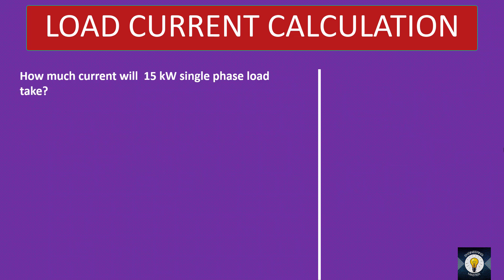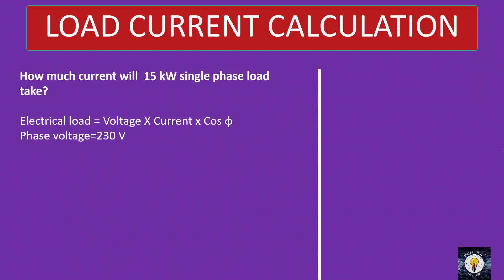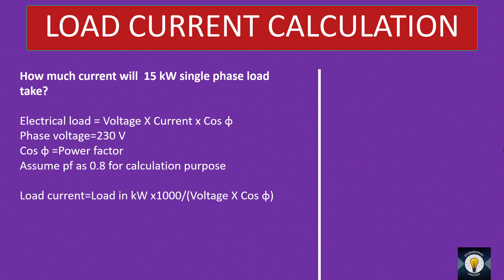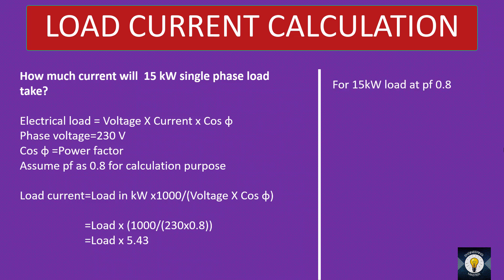In the case of single phase, let's solve a problem. What is the current consumed by a 15 kW single-phase load? For single phase, electrical load equals voltage into current into cos φ. Voltage is phase voltage — my phase voltage is 230 V. Assuming power factor 0.8, load current equals load in kW into 1000 divided by voltage into cos φ — that is load into 1000 divided by 230 into 0.8 — which gives load into 5.43. So for a 15 kW load at power factor 0.8, load current is 15 into 5.43, which equals 81.45 A.